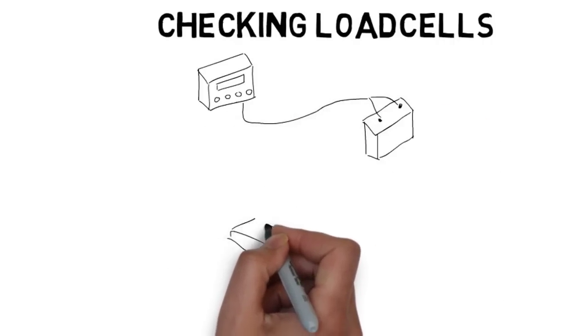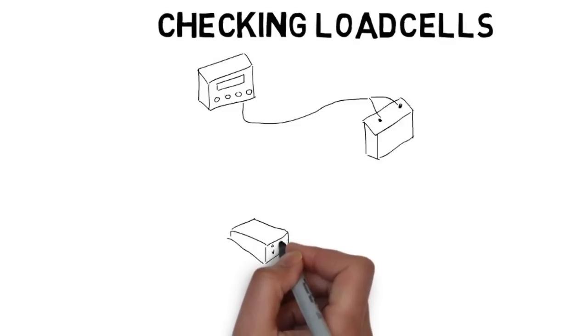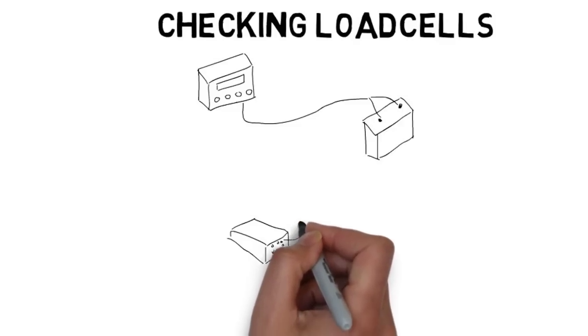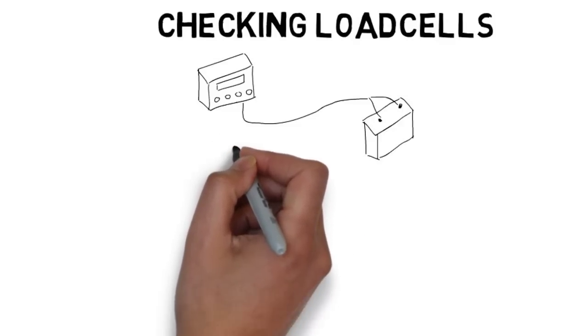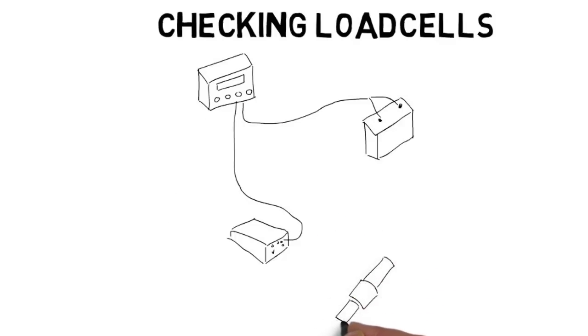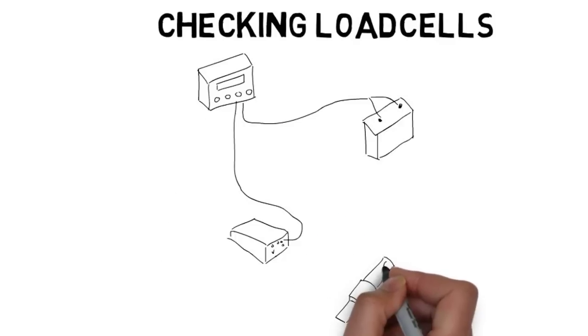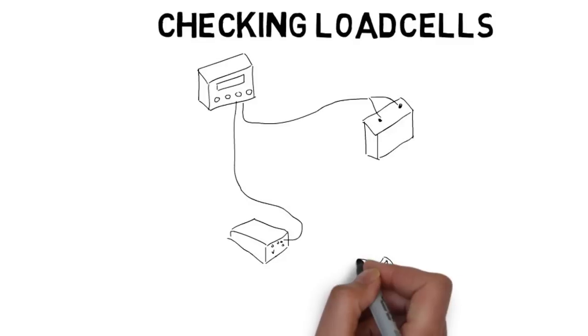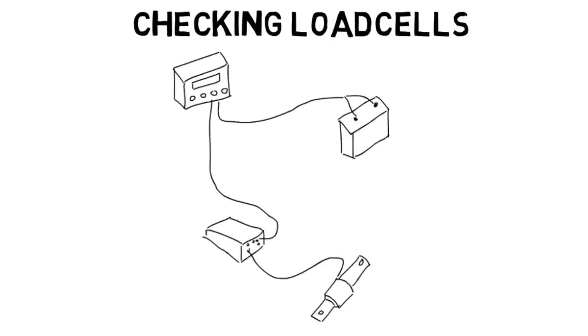There are three parts to testing a load cell. First, after the load cell is connected, zero out the indicator. Ensure the scale stays stable at zero. If it drifts or says plus or minus range, that means the load cell is bad.